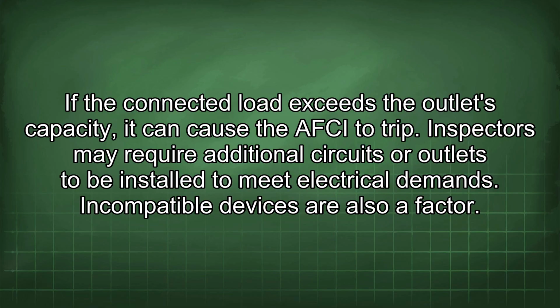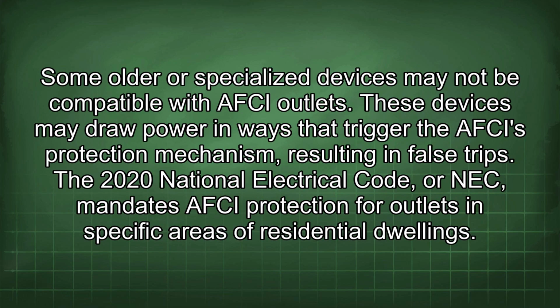Incompatible devices are also a factor. Some older or specialized devices may not be compatible with AFCI outlets. These devices may draw power in ways that trigger the AFCI's protection mechanism, resulting in false trips.